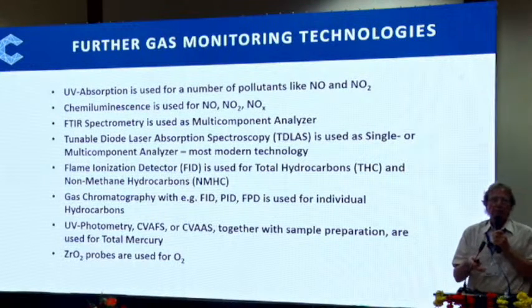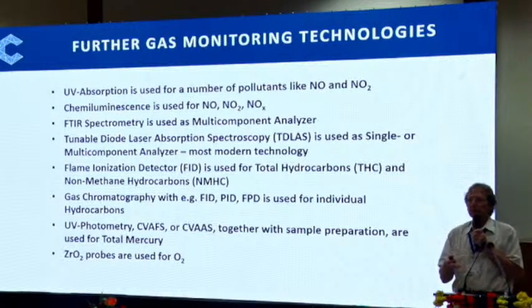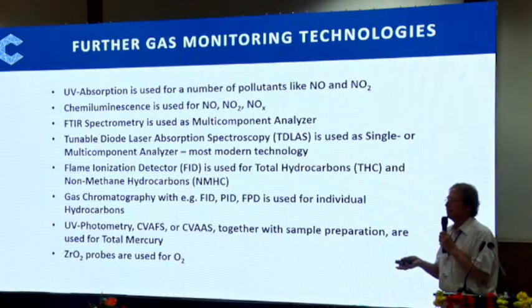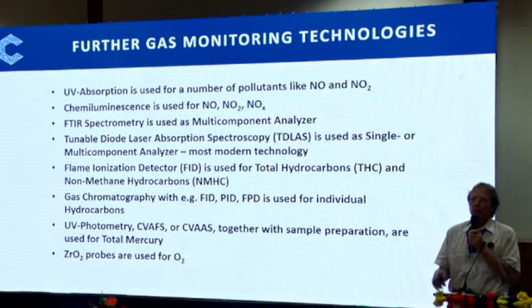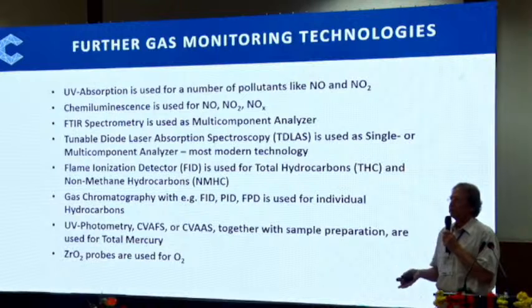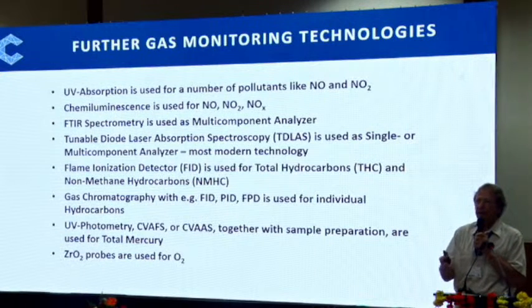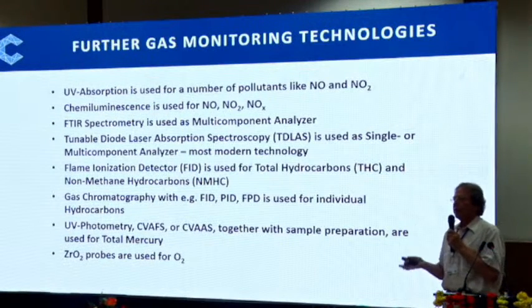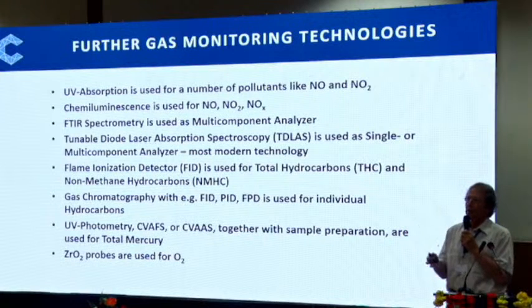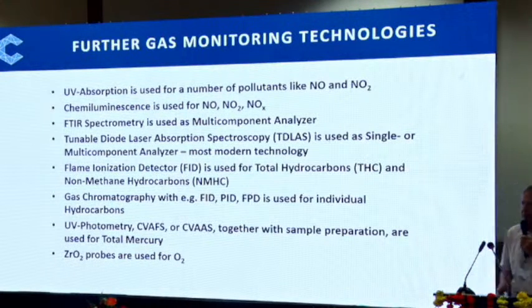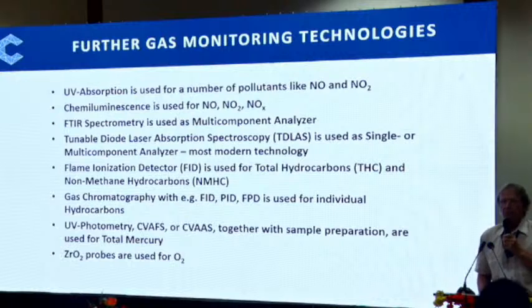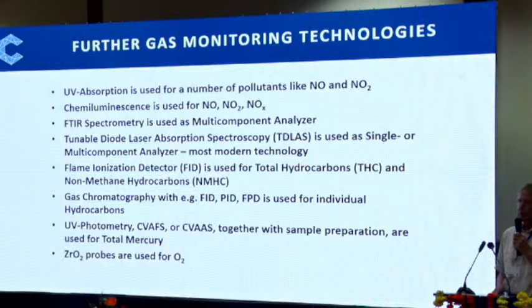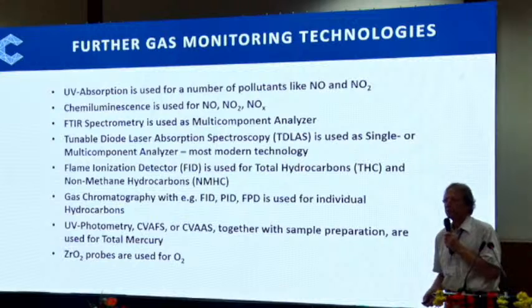Or if I want to see individual hydrocarbons in my emissions, for whatever reasons, or in process monitoring, even more important, I want to see an individual hydrocarbon, then I'm looking into gas chromatography. Then UV photometers, or cold vapor atomic fluorescence spectrometers, or atomic absorption spectrometers, that's used for mercury. And then, as already mentioned, zirconium dioxide probes for oxygen.